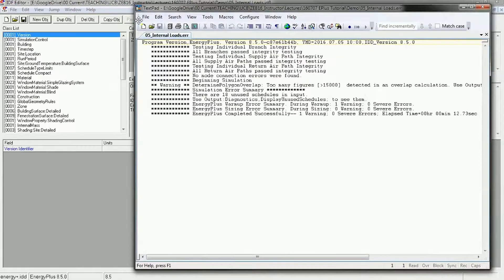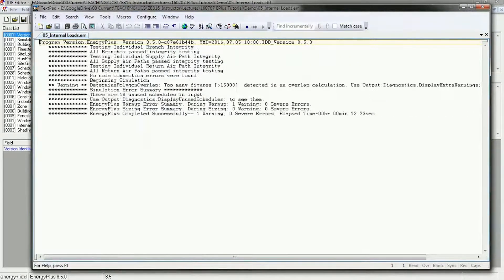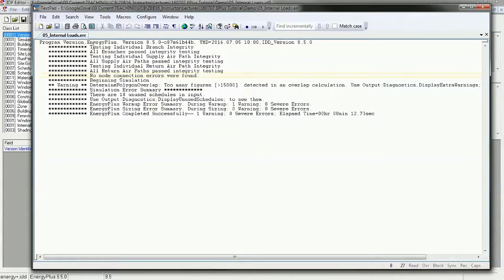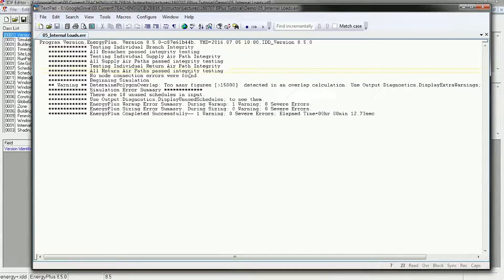These error messages are usually written in pretty good English, so try reading them and see what you can tell. If you've got questions feel free to email. What this says is: testing the branch integrity — all branches passed testing; individual supply air — remember this is a mixed air zone model so it's making sure it finds a volume of air; all supply air paths passed; return air passed; no node connection errors were found.